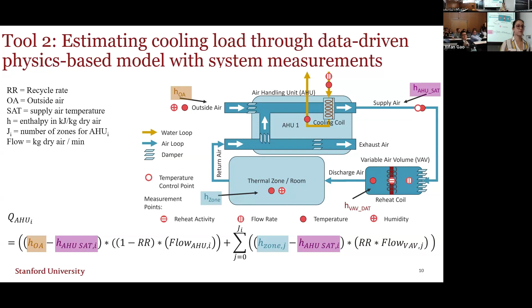What happens is I calculate the enthalpy of the air at different points, which takes into account both temperature and humidity. I attribute the differences between the enthalpies to the air conditioning — the difference in enthalpy tells me whether the AC provided cooling or heating, as in the case of the VAV.